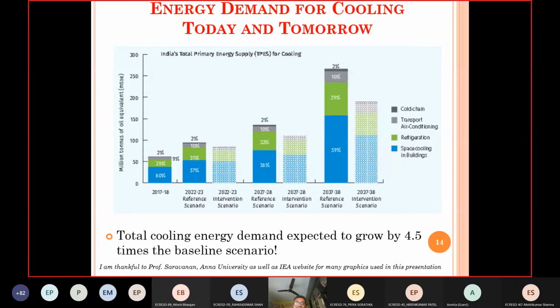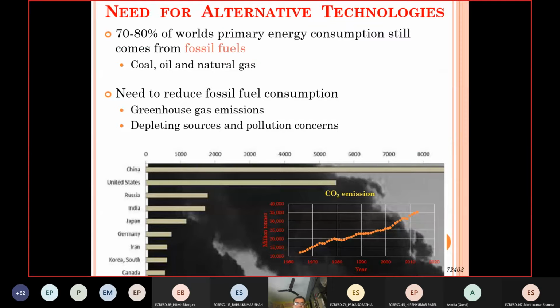But this can be reduced, as shown by those hazy columns, if an intervention is done. That is, you change your normal course and adopt all required steps to reduce the energy demand from air conditioning. You are not compromising on your tons of refrigeration, but you are trying all the required steps to reduce the kilowatt per ton of refrigeration demand. Total cooling energy demand is expected to grow by 4.5 times the baseline scenario. One of the concerns related to the use of energy is greenhouse gas emission and other pollution-related concerns.